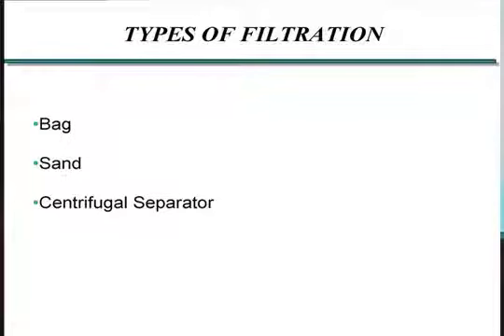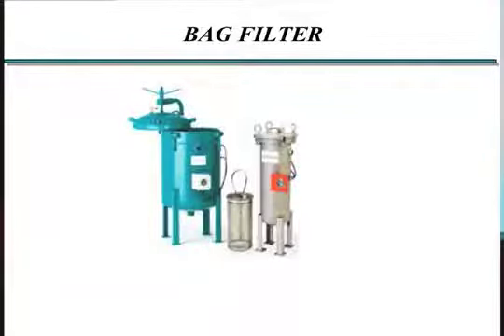We'll talk about 3 types of filtration you typically see: bag or cartridge type filters, sand filters, and centrifugal separators. Jump right into bag filters. These are pretty simple devices. You've got some sort of canister that has a cartridge of some sort of media in it that the water runs through. It's got a small pore size, strains out the particulates. It's pretty much what we think of when we think of a filter.